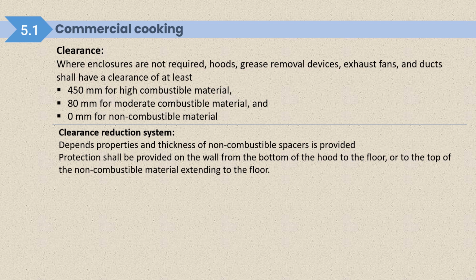Protection shall be provided on the wall from the bottom of the hood to the floor or to the top of the non-combustible material extending to the floor. So full height protection is required.